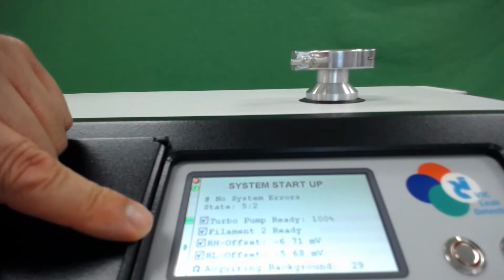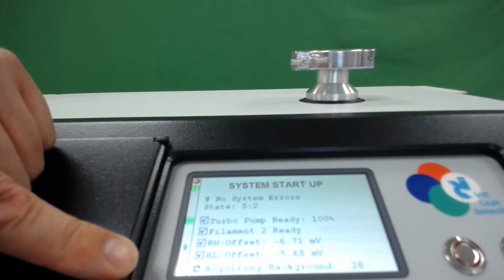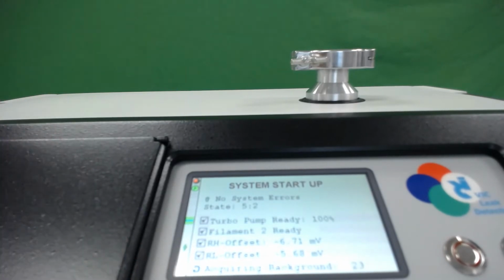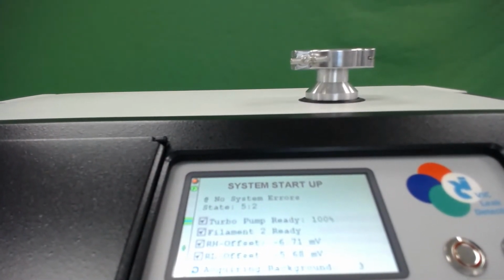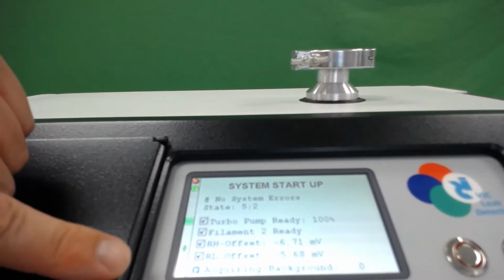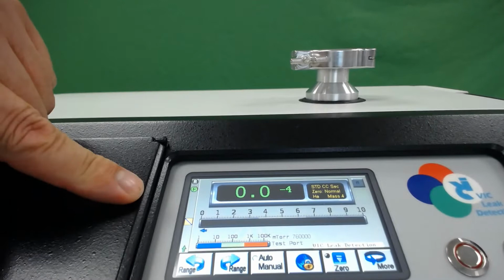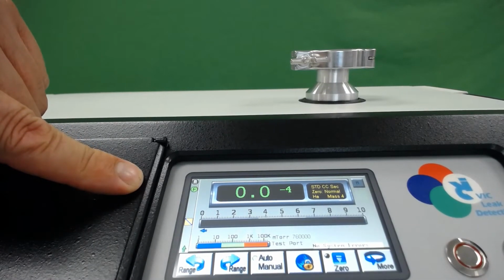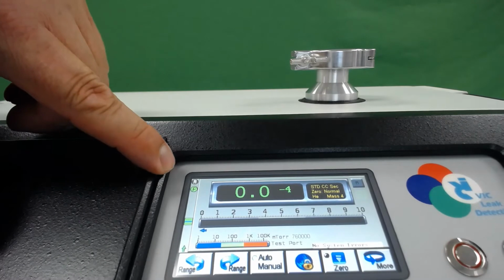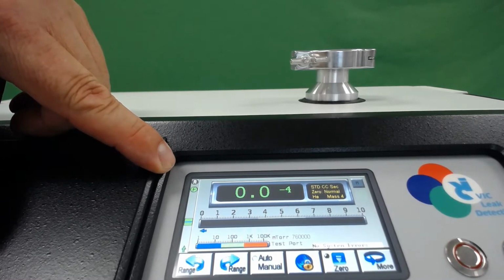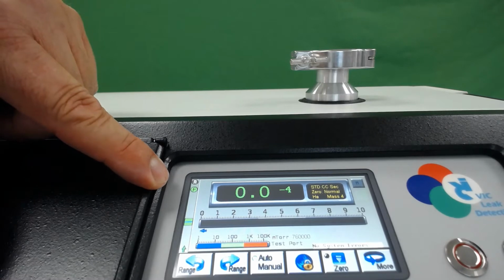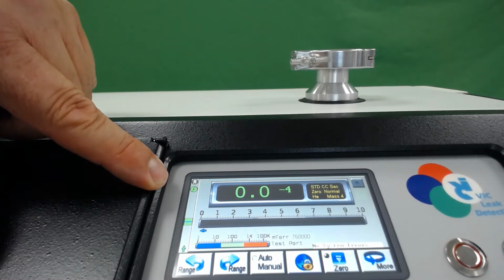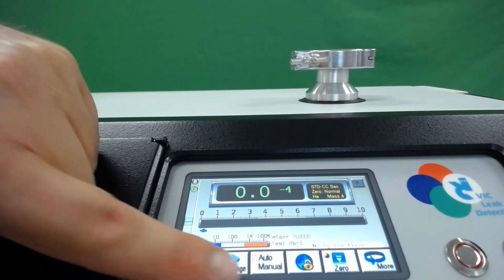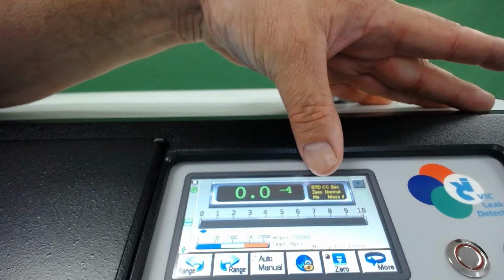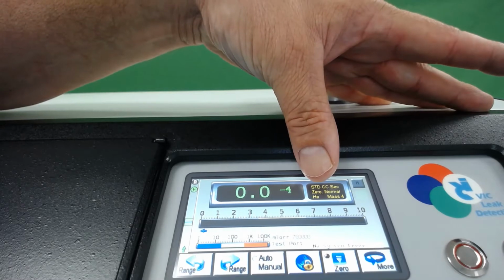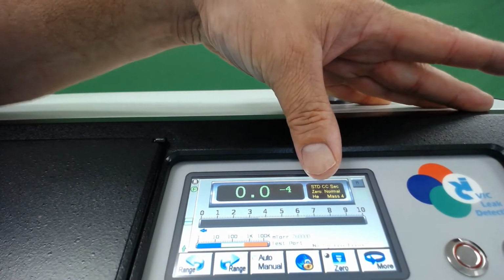The machine checks the offsets and now begins an acquisition of background, and that will take approximately 30 seconds. Ready? Once the background acquisition is complete, the system throws up the main monitoring screen and indicates it's ready for testing. The R in the upper left-hand corner indicates the machine is ready. The F in the green balloon tells you the filaments are on. The machine is in an automatic ranging mode. We're in standard cc's per second, normal zeroing mode, and the machine is set to detect helium, mass 4.